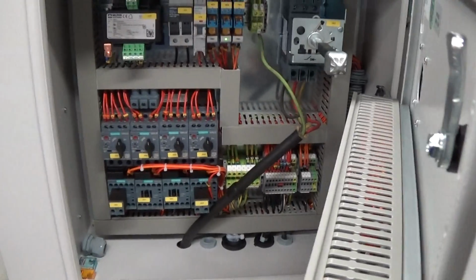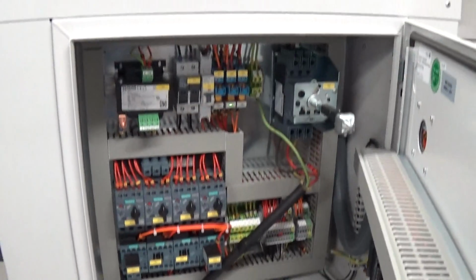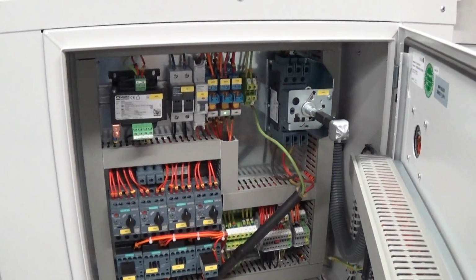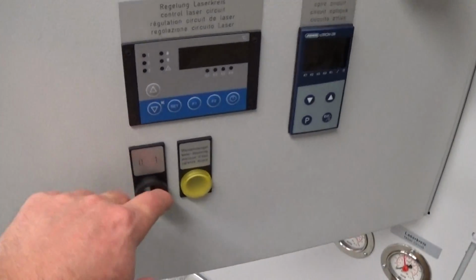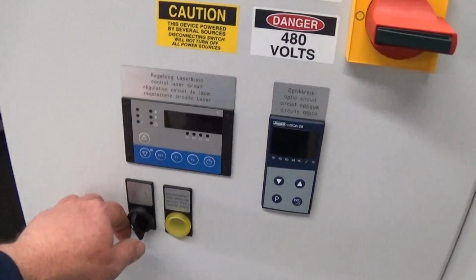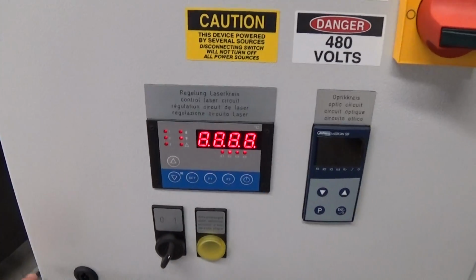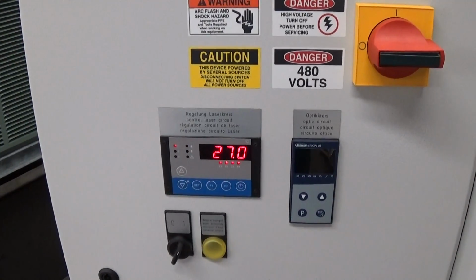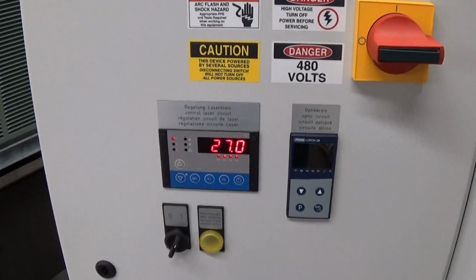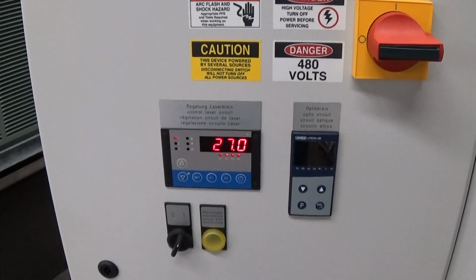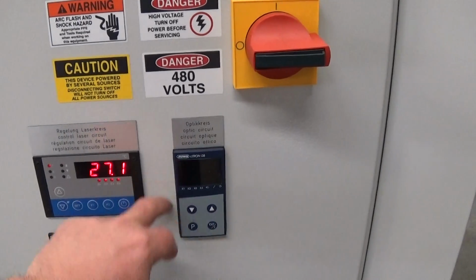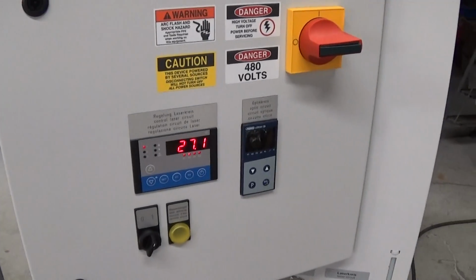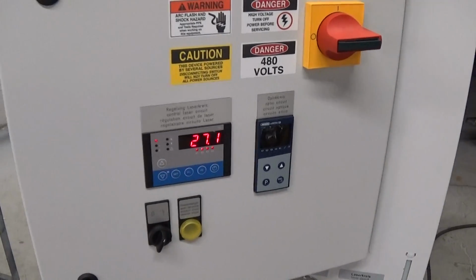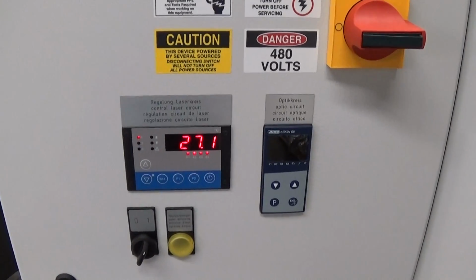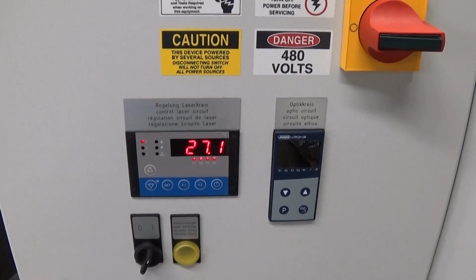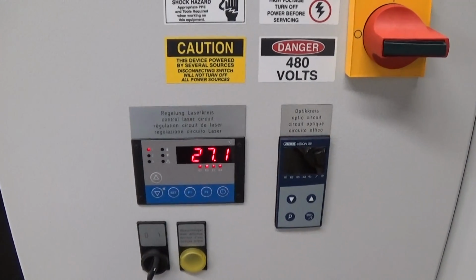So obvious stuff. This unit was set up originally to have the ability of a remote on-off start. We've jumpered that, and we've actually added in this simple on-off switch. Okay, so we are going to turn the unit on. When that happens, the controller just kind of goes into a little stall mode just for a second. Then you can see it comes up to show what the temperature of the process setting is. This you'll never see on for the application this is going to be used for. So this has a temperature rating, a low of about 12 C, which I think is what, 52 Fahrenheit or so. And for this application, that's fine.